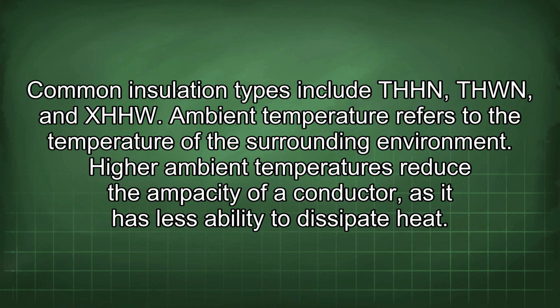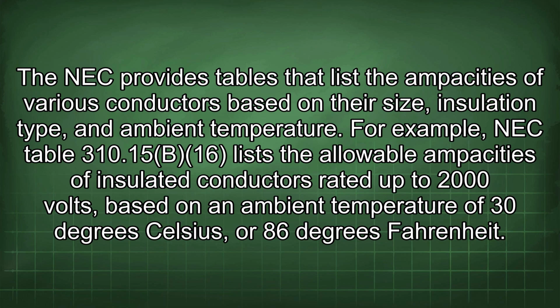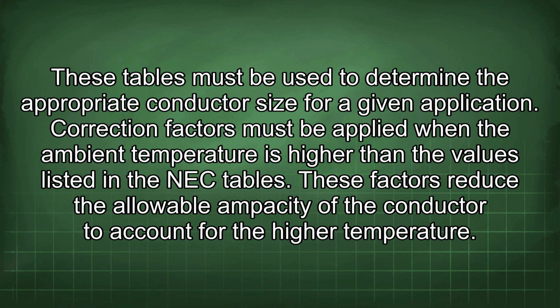Ambient temperature refers to the temperature of the surrounding environment. Higher ambient temperatures reduce the ampacity of a conductor, as it has less ability to dissipate heat. The NEC provides tables that list the ampacities of various conductors based on their size, insulation type, and ambient temperature. For example, NEC Table 310.15(B)(16) lists the allowable ampacities of insulated conductors rated up to 2000 volts based on an ambient temperature of 30 degrees Celsius or 86 degrees Fahrenheit. These tables must be used to determine the appropriate conductor size for a given application.